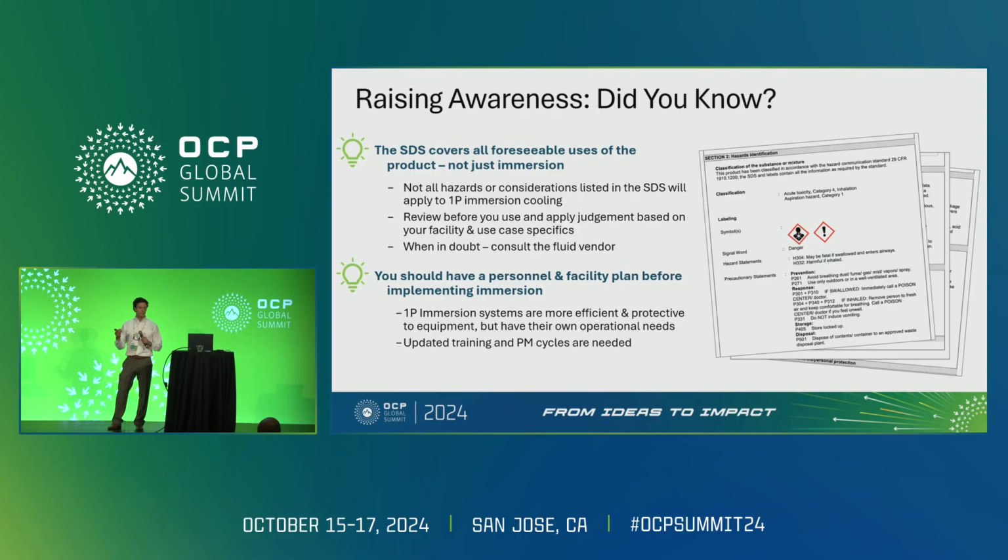So if you see a warning concerning mist generation, that might not be as relevant in the immersion cooling space, where we don't expect to generate a lot of mist like you might if you're using one of these fluids in metalworking. So it's important to recognize that you really have to be knowledgeable of your end use and consult with the fluid provider if these risks are applying to your use case.